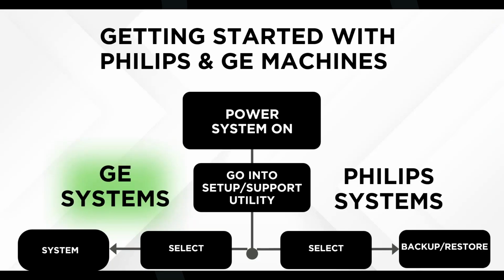So typically, if there's ever an issue with GE systems, one of the first things that they would ask you is what R level is the system, and you can find that over here under the system image type number, R9.1.2, and this is the software revision level for the particular system that you have. So if for some reason it was just bricked and you tried to power it on and you would get nothing, maybe just a GE logo or an error code, and you couldn't get to this page, sometimes the backup can help you with that if it's labeled properly. So I like to label all my backups with the time and date, what R level it is, and what R level of the system it is, as well as the system serial number.